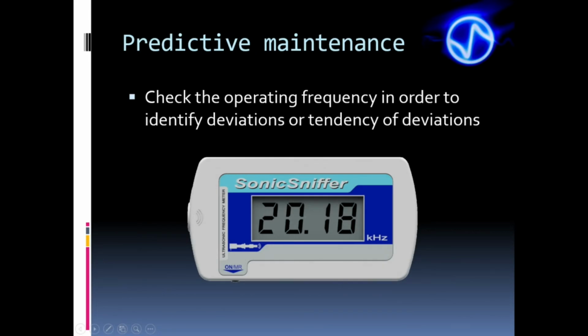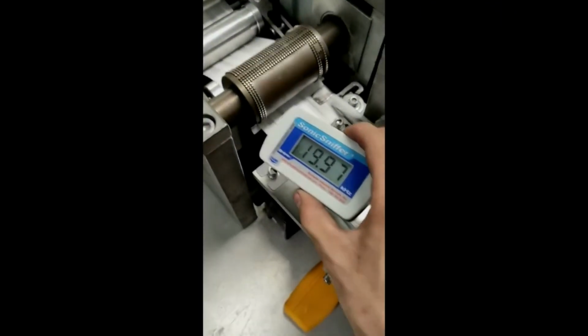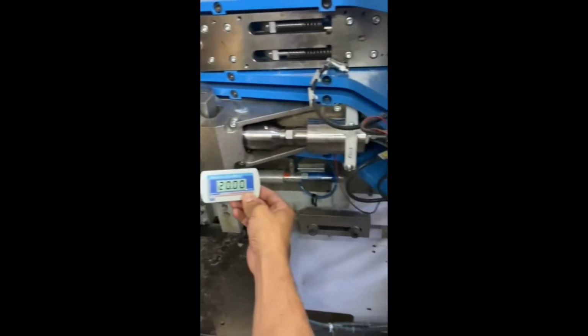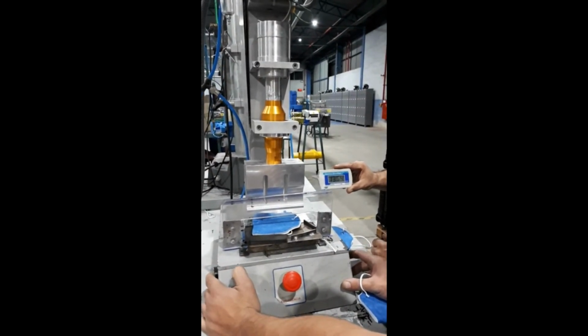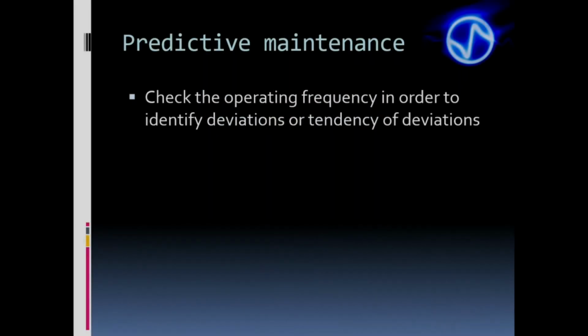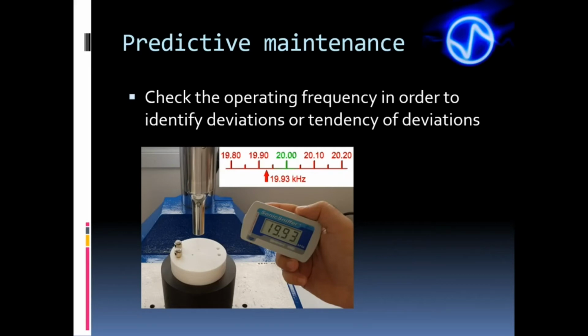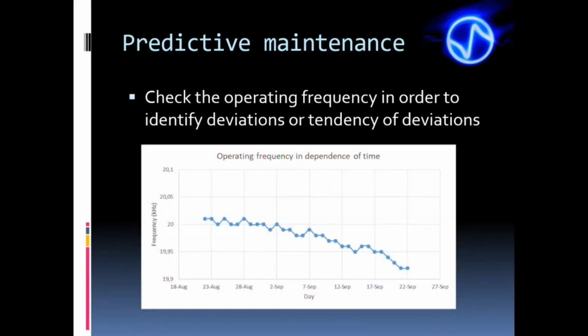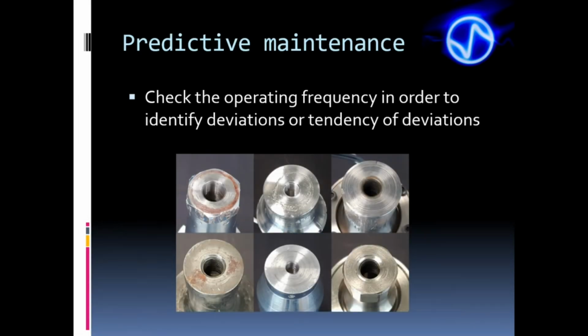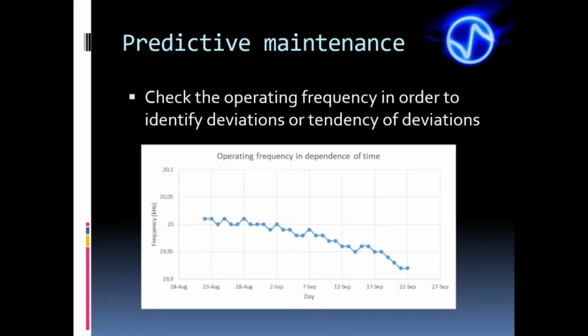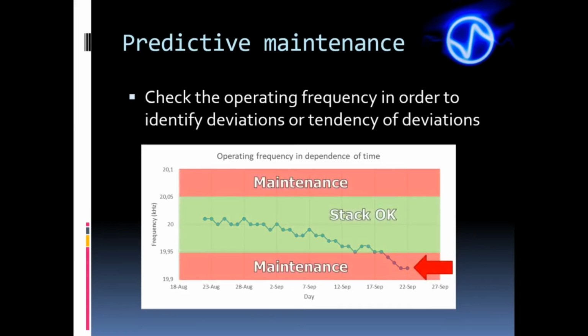To measure the frequency, we can use the sonic sniffer. The sonic sniffer is a non-contact ultrasonic frequency meter. It measures the operating frequency of the acoustic stack during the operation, without having to remove the stack from the machine. Thus, measurements are faster and much more practical. To monitor the stack, we can, for example, once a day, measure the frequency of the welding machines and note the measured value. With this data, it is possible to monitor the evolution of the stack's frequency as it wears out. Interface and sonotrode degradation is a slow process, but it is constantly happening. From the frequency deviation detected by monitoring, we can identify the need for preventive maintenance according to the tolerance specified by the manufacturer of the welding system.